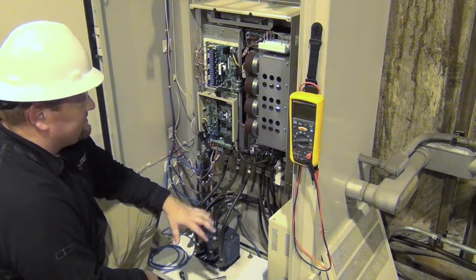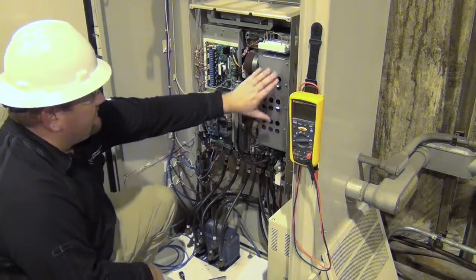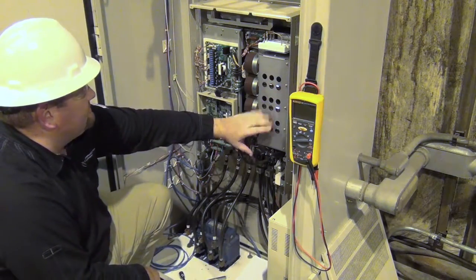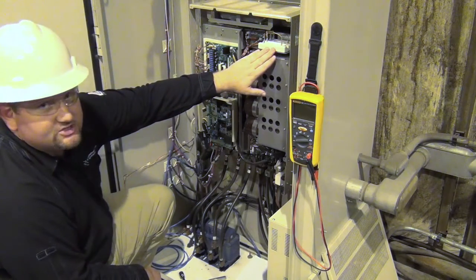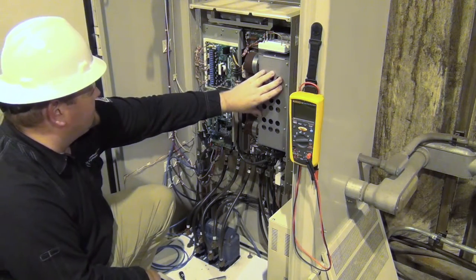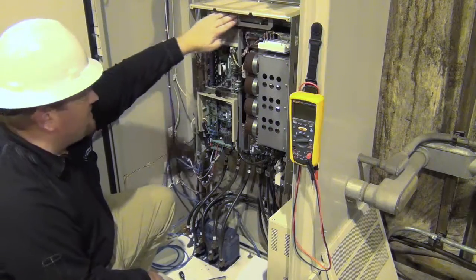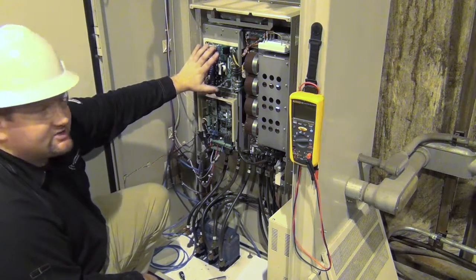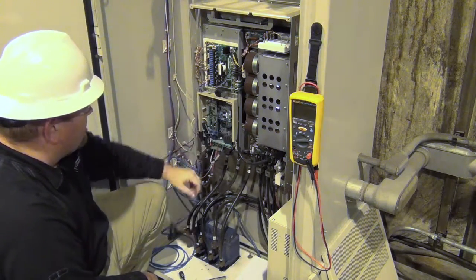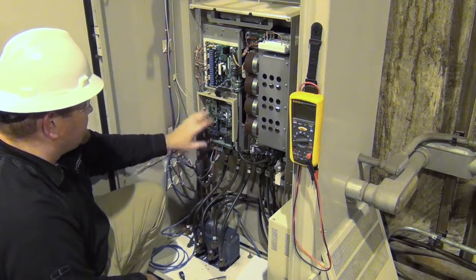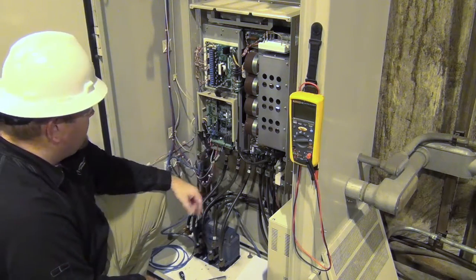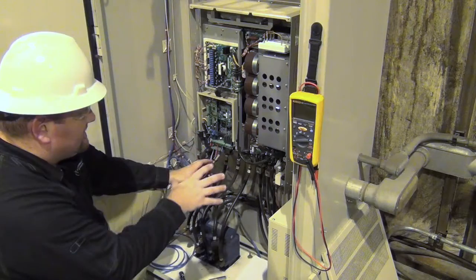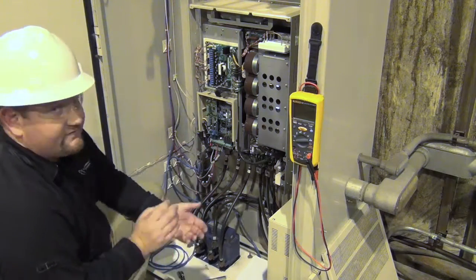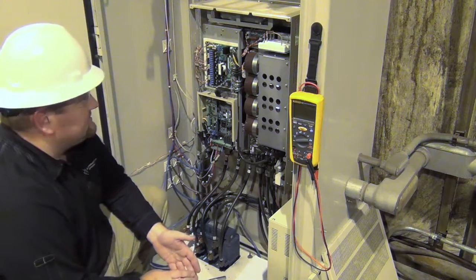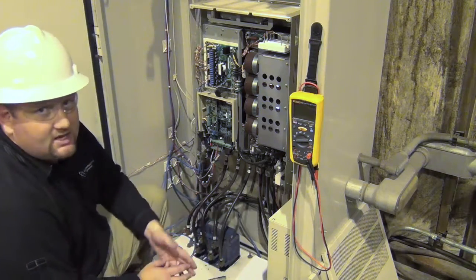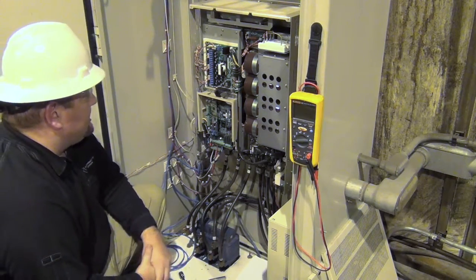So the different components that we have in front of us, we have the DC bus capacitor section, we have the soft charge and the bleed off resistors for the capacitor, there's a fan carrier at the top, our gate driver board, and our control boards. This particular drive has a couple of option cards on it. So what we're going to do is continue checking all of the control terminals, verify all the control and power connections that we can get to. Again, are snug, secure, no loose connections.